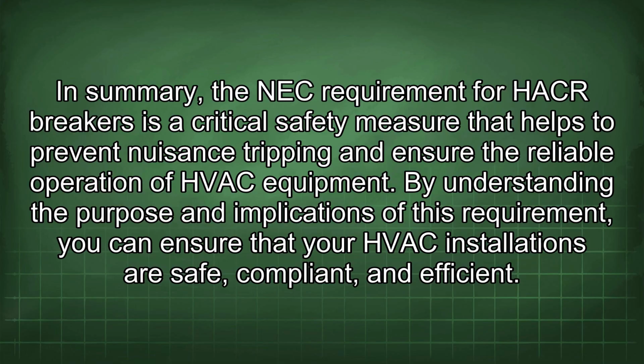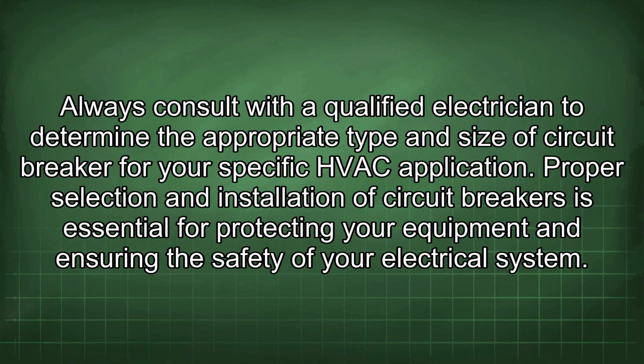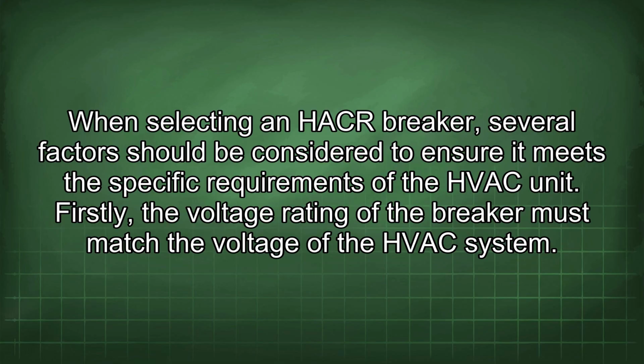By understanding the purpose and implications of this requirement, you can ensure that your HVAC installations are safe, compliant, and efficient. Always consult with a qualified electrician to determine the appropriate type and size of circuit breaker for your specific HVAC application. Proper selection and installation of circuit breakers is essential for protecting your equipment and ensuring the safety of your electrical system. When selecting an HACR breaker, several factors should be considered to ensure it meets the specific requirements of the HVAC unit. Firstly, the voltage rating of the breaker must match the voltage of the HVAC system.